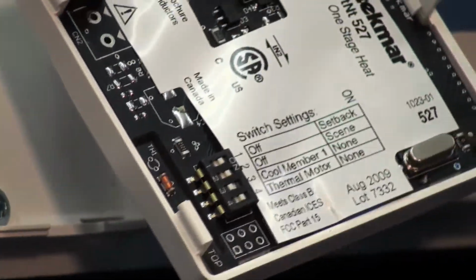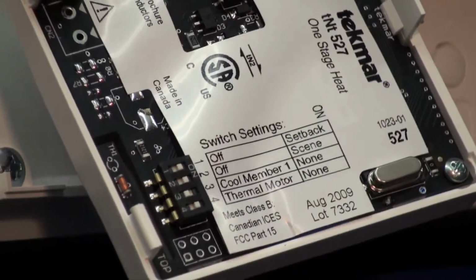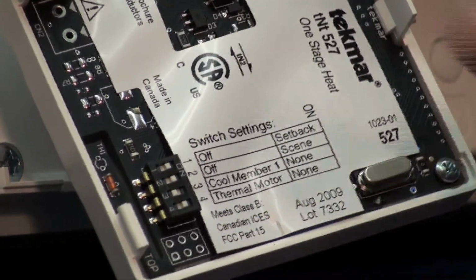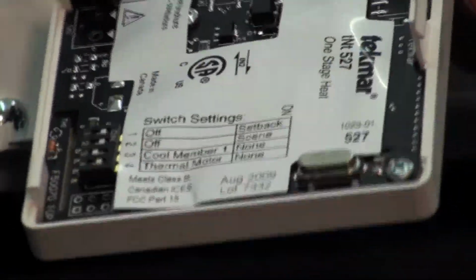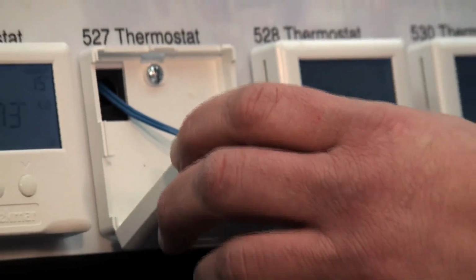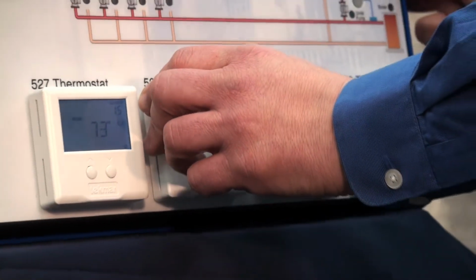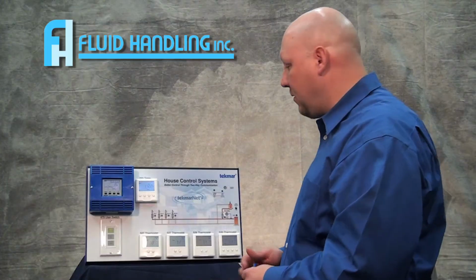Then if I have a thermal motor, a hot wax zone drive motor connected to it, I can tell it that's on there also. So those are your 4 dip switch settings. To put the cover back on, you're simply going to latch the bottom 2 hinges and tip it up until it snaps into place and you're remounted.